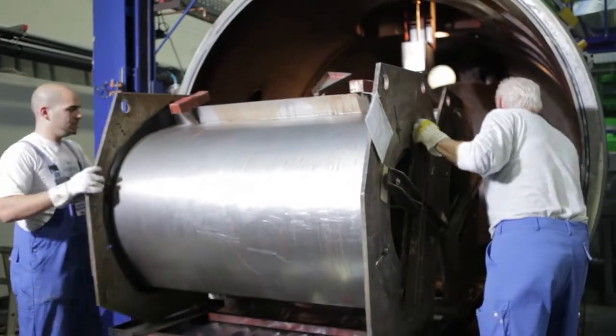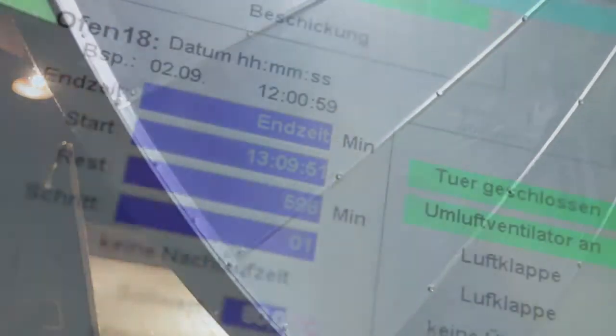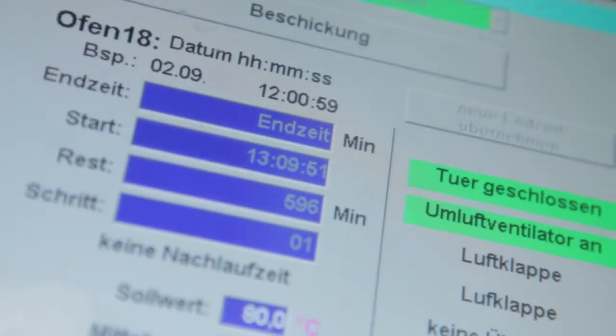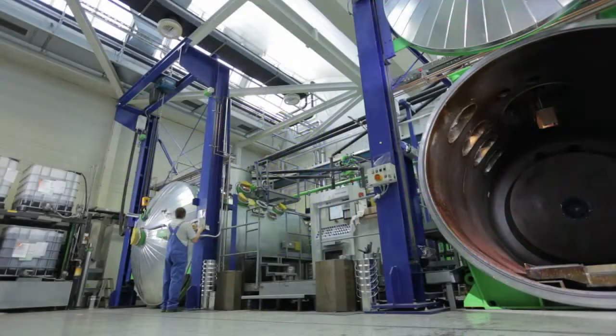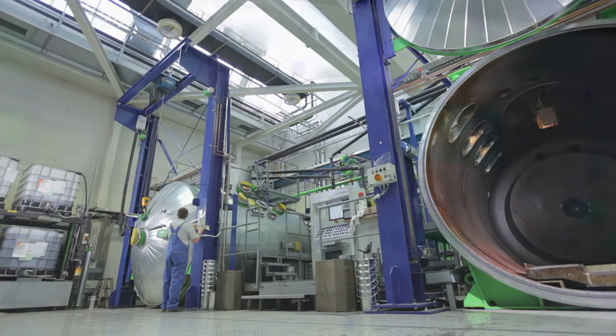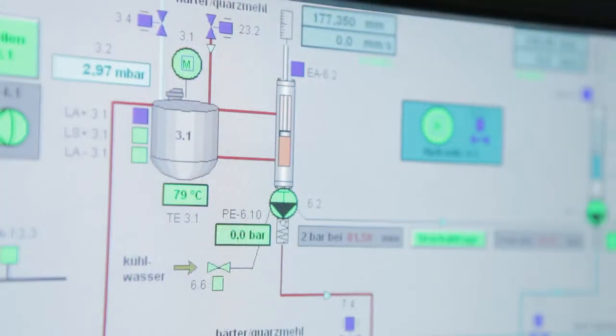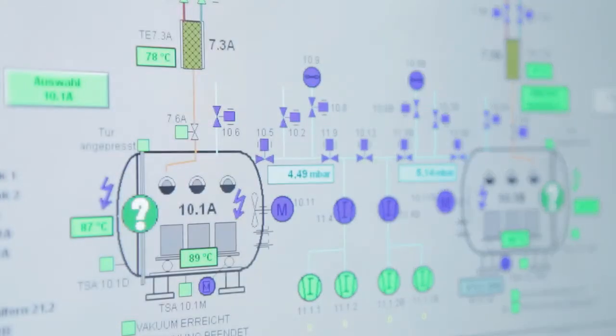The real secret of the GEAFOL technology lies in how it is made. Together with a cast resin, the coils are cast into a solid block in a vacuum furnace. Because aluminum and cast resin expand at a similar rate when exposed to heat, the mechanical stress remains minimal, even when exposed to extreme changes in temperature.